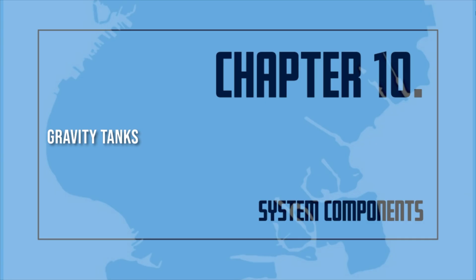Tanks may be located on the tops of buildings or raised on tall supporting towers. The water pressure in a gravity tank system depends on the elevation of the tank. This is the main advantage over other kinds of systems. For every 1 foot the tank is above the discharge outlet, 0.433 pounds per square inch of water pressure is generated. In other words, the higher the tank elevation, the greater the water pressure. The gravity tank is extremely reliable.